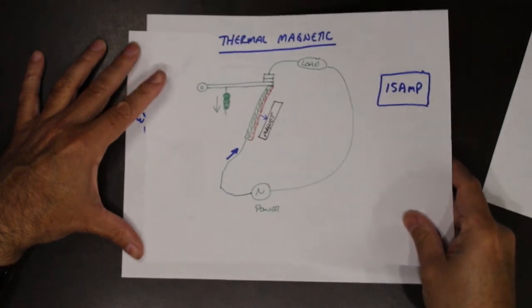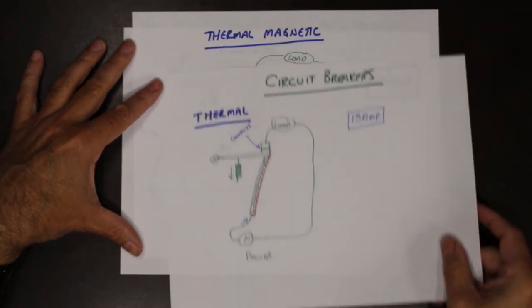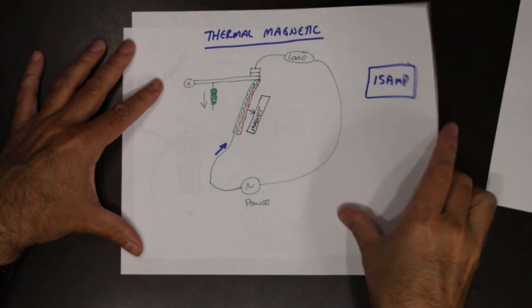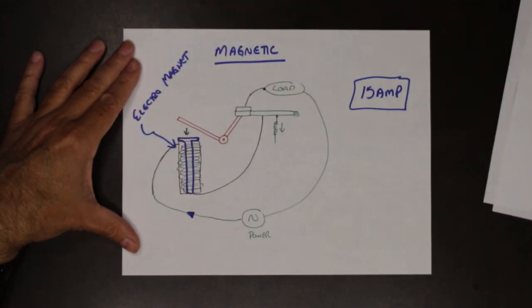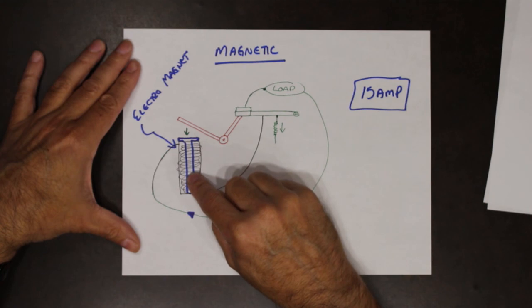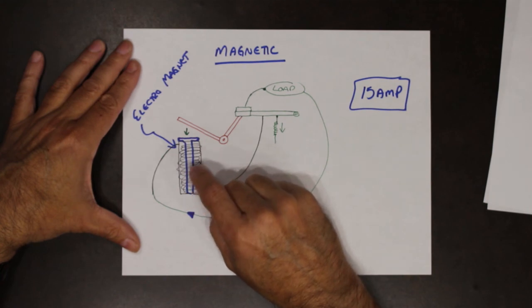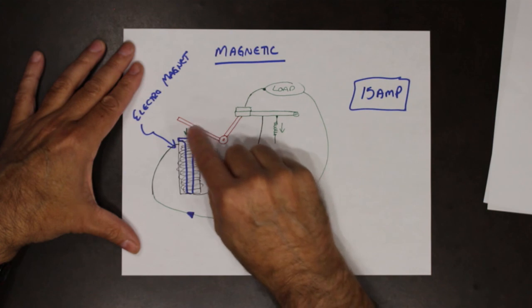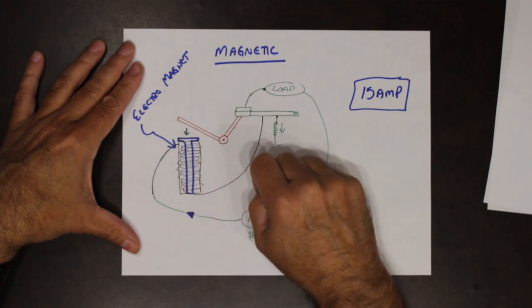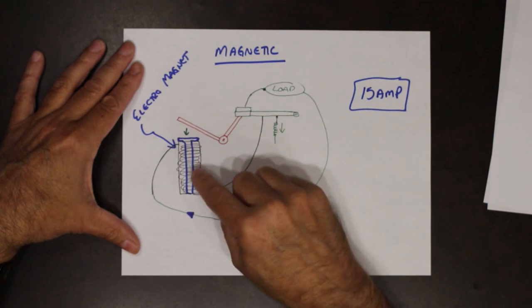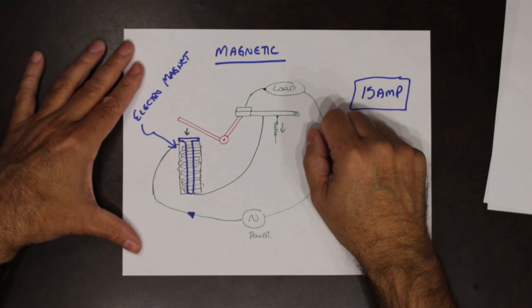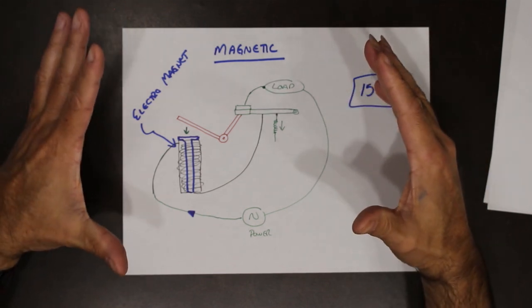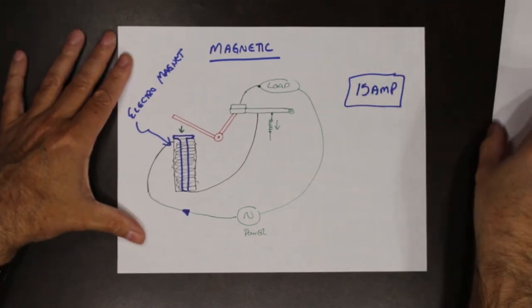Now, on the other side, these two are not affected by any electromagnetic interference. Depending on the placement of this, we could have electromagnetic interference that interferes with creating this magnetic field. Could prematurely cause it to trip, or cause it not to trip at all. So each has its advantages and each its disadvantages.